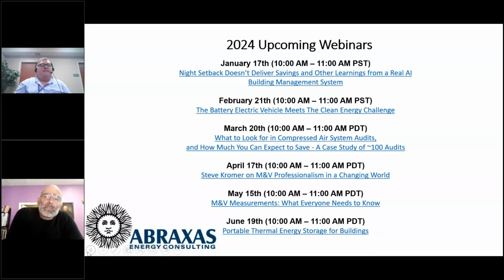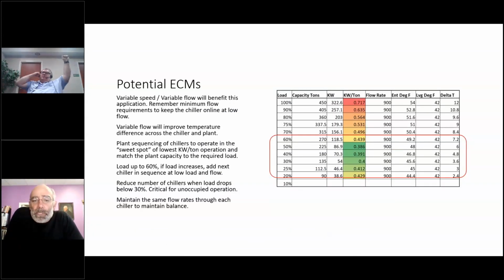So I've got a question, can you go back a slide? This one confuses me. First off, where did you get this kilowatt per ton at all these different loadings? Did you calculate it with curves you got from somewhere, or did you actually measure the flow rate and delta T and calculate it yourself? A lot of this chart came from the manufacturer, this was their submitted data. They may have done it in 10% increments, and then I added the 75%, the 25%. Typically they might give you 10, 20, 30 percent points.